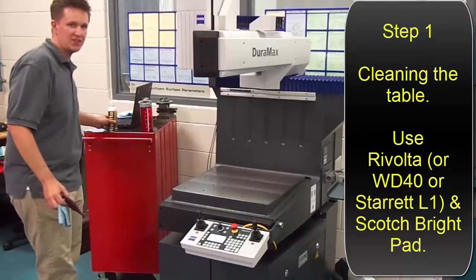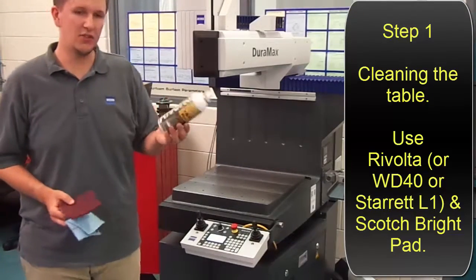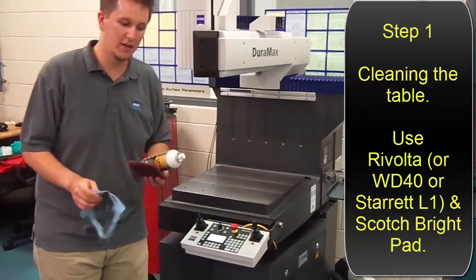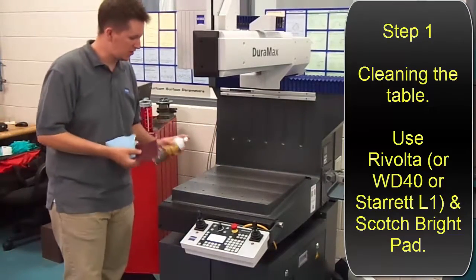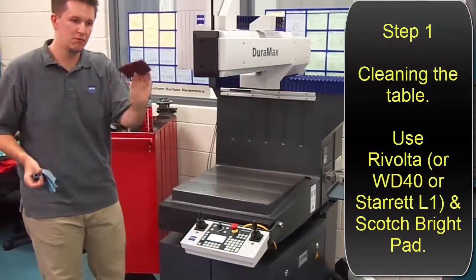The first thing people ask is how to clean the table. Zeiss has this product called Rivolta. It's something similar to WD-40 or CRC 556. It's just an aerosol spray. You can just spray it on the table. I like to take a little Scotch pad, nothing fancy.